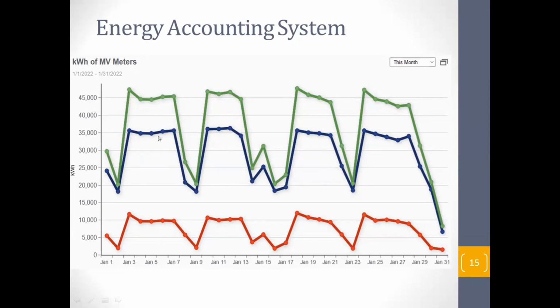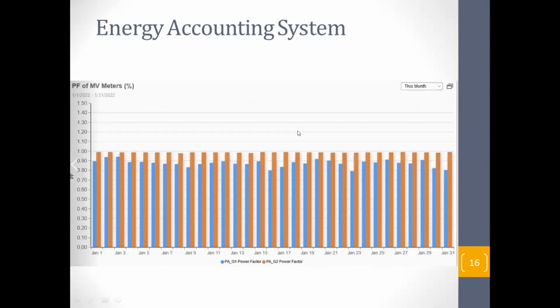So they have 2 feeders, the red one and the blue one. These are direct information coming from the meter. And the third one is green. This is not direct information. This has been calculated through a formula and presented. All 3 can be presented like this. So there are similar presentations, like you can get power factor, and they do have power factor in their medium voltage system.